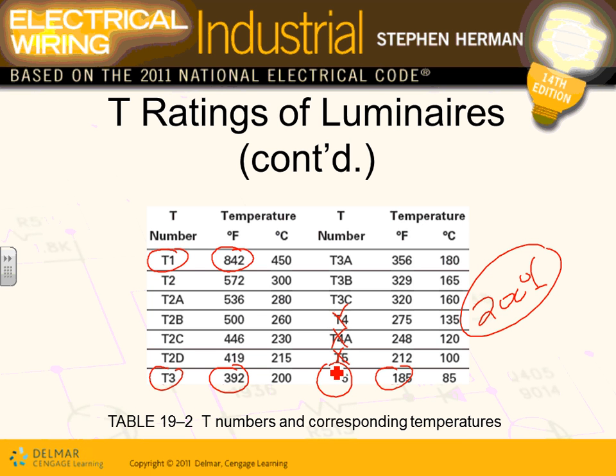Any questions about the T rating of a lighting fixture? That's how they pick a lighting fixture in a Class 1, Class 2, or Class 3 location. You can see the higher the number for T's, the lower the temperature. The lower the temperature, meaning that fixture doesn't really get hot at all. It doesn't ignite the surroundings. Any comments about the T rating of these fixtures? T rated, you're going to hear them all the time.